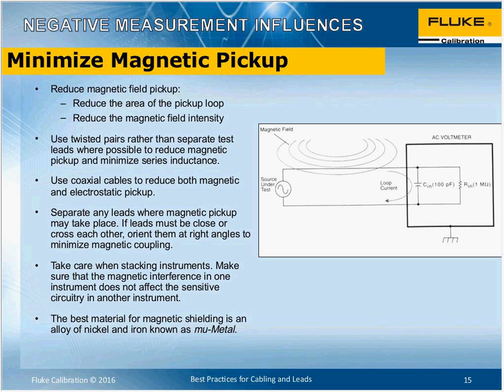Likewise, the converse happens in reverse. If you've got a sensitive measurement, twist the leads together. Better still, twist them and put a shield around them. Keep the leads away from anything that might cause interference to be picked up as well. Also be aware that the same thing can happen with the instruments themselves.